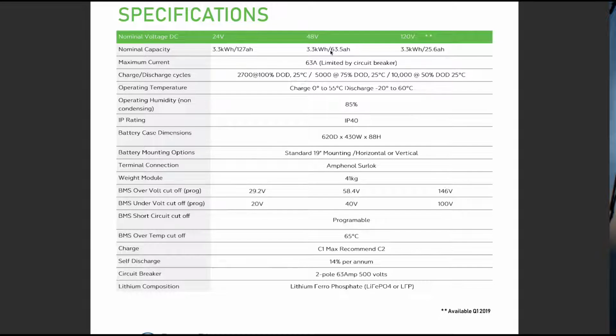So therefore, 144 kilowatt hours total. For those of you who are familiar with lead-acid batteries, you know that that 100% figure is not the usable capacity. And the usable capacity is based on how long you want those cells to last. A popular figure used for a good lifespan for a lead-acid battery is around 50% usable. So of that 144, if we divide it by 2, it's going to give us 72 kilowatt hours usable. There we go. So that's our usable energy.